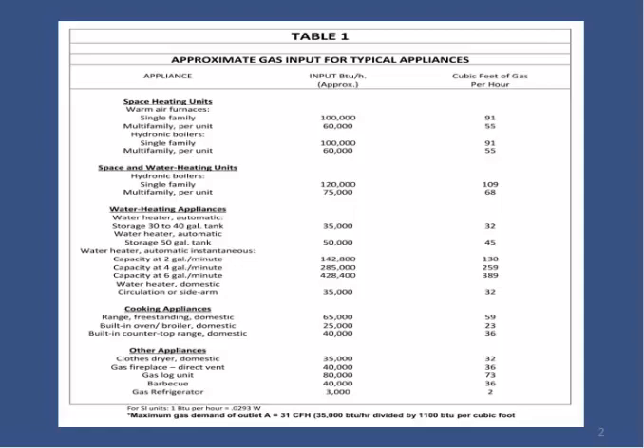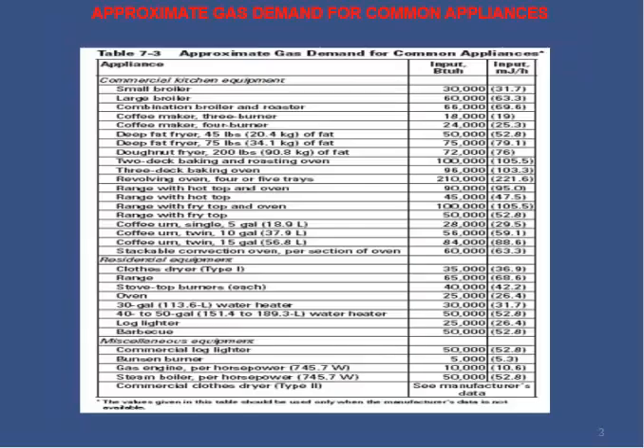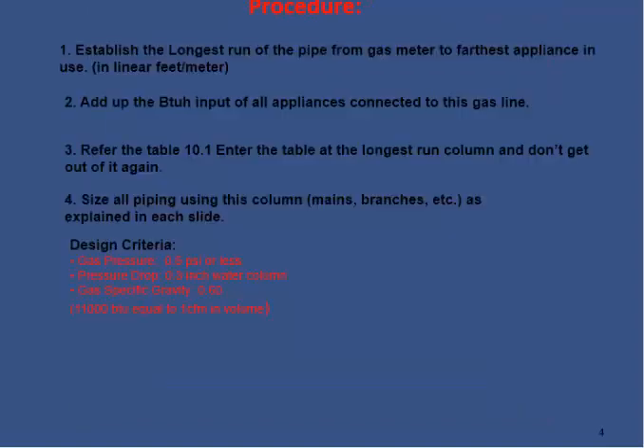Similarly, here we see a table giving the input required for domestic appliances. The procedure for designing the pipe sizes is as follows: Number 1, establish the longest run of the pipe from the gas meter to farthest appliance in use, in linear feet or linear meter. Then add up the BTU input of all appliances connected to this gas line.